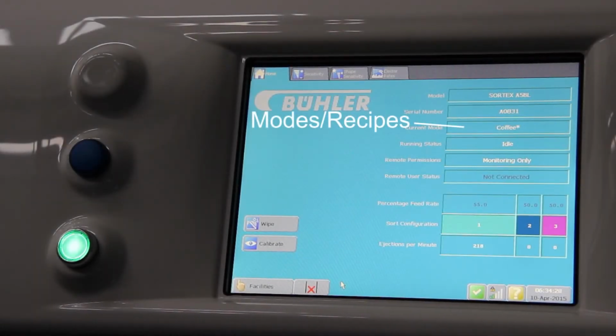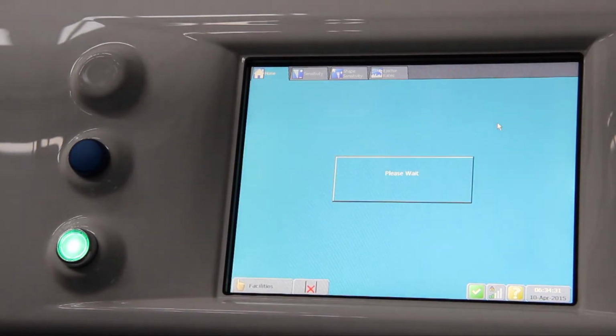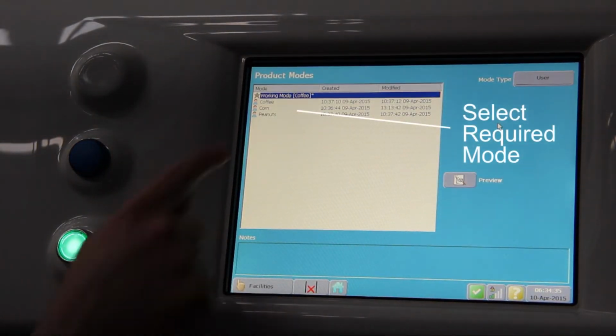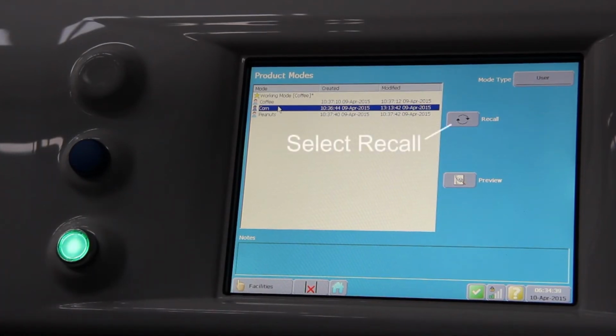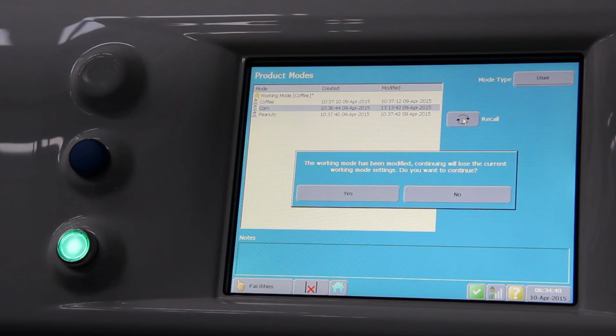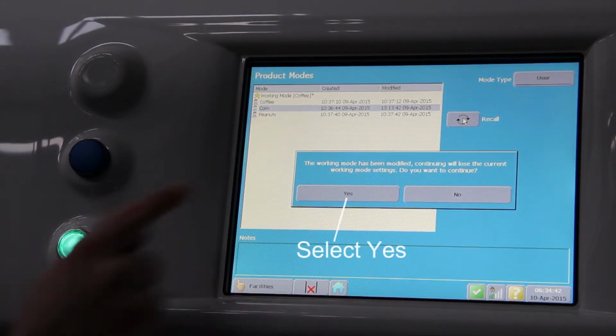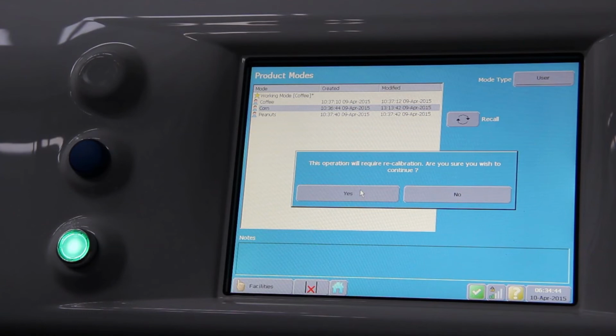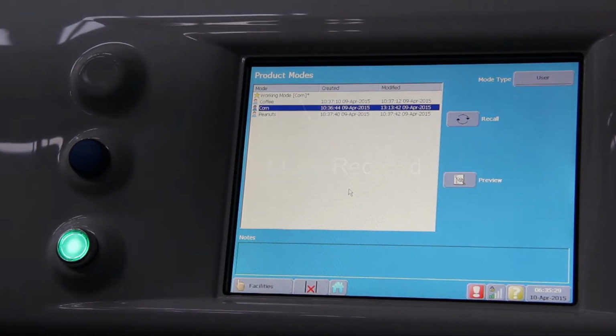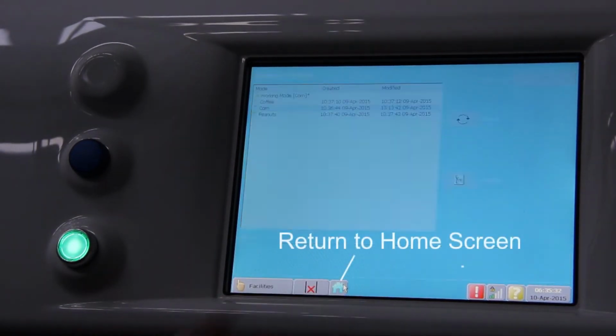To change the working mode, select the current mode on the home screen. Select the required mode from the list and select Recall. A window will appear warning that the working mode has been modified. Continuing will lose the current working mode settings. Do you want to continue? If there have been no significant changes which will require saving on the current mode, then select Yes. A window will appear warning that recalling the mode will require a calibration. Select Yes to continue. The working mode will change to the recalled mode with all the sorting parameters specific to the product. Return to the home screen.